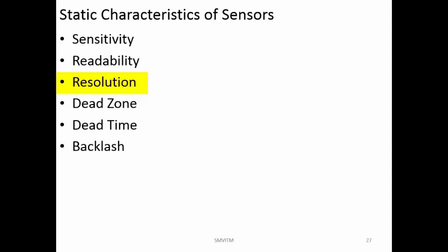As the resolution increases, the amount of data that is created also increases. You have to have more and more accurate systems. It is not a good thing to have a very small resolution but very poor accuracy. Then your system is not going to function efficiently. So usually the accuracy should be half of the resolution. If your resolution is say 0.1 volts, then the accuracy should be half of it: 0.1 divided by 2, so the accuracy should be plus or minus 0.05. If it is more than that, then even though you have a very small resolution, the instrument is not going to have any usage. You are simply wasting money buying very high resolution because the accuracy factor is going to cancel out whatever advantage you get.